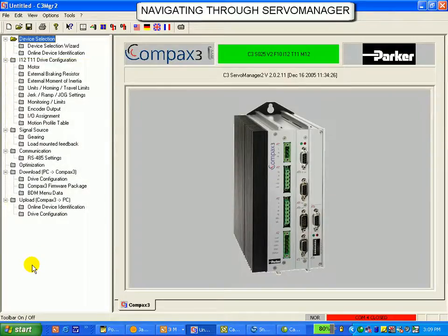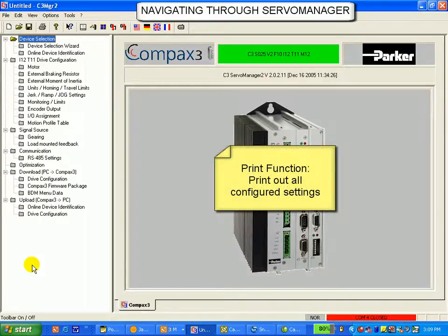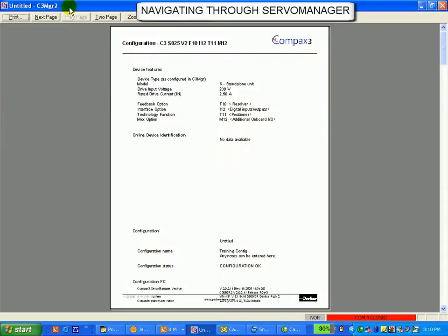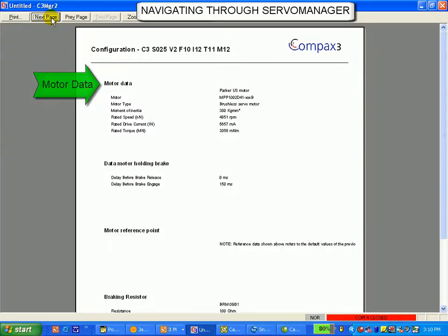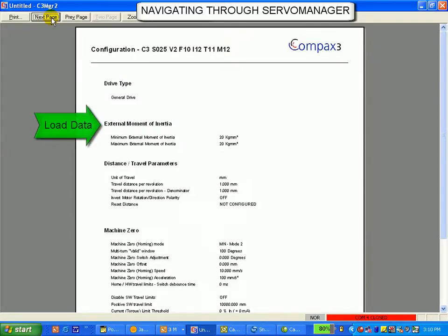First, I would like to discuss one point under the file icon, and that is the print function. The print function allows you to print out the complete configuration of the drive. I have a complete configuration loaded right now, and I will go to the page preview screen so you can see this. Here I can see the complete configuration of my drive. All the data you have entered in the configuration is contained here and is an excellent documentation piece for your customers to ship with their machines.